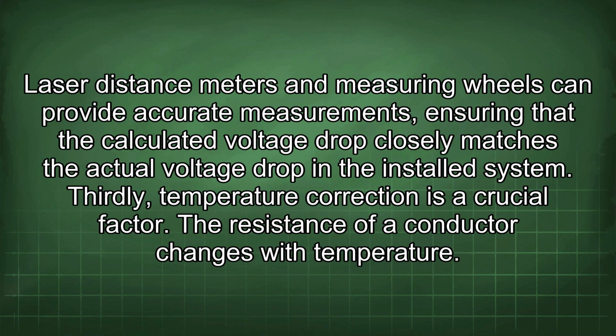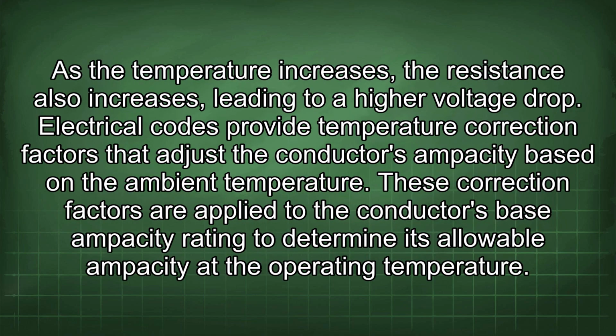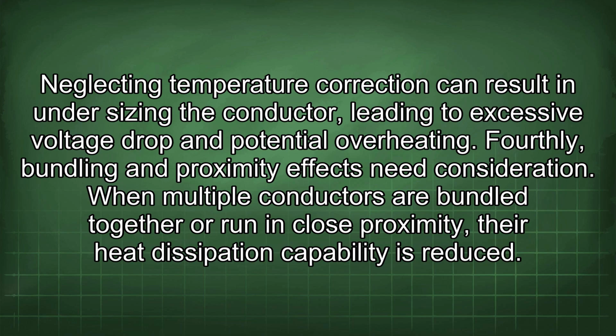Thirdly, temperature correction is a crucial factor. The resistance of a conductor changes with temperature. As the temperature increases, the resistance also increases, leading to a higher voltage drop. Electrical codes provide temperature correction factors that adjust the conductor's ampacity based on the ambient temperature. These correction factors are applied to the conductor's base ampacity rating to determine its allowable ampacity at the operating temperature. Neglecting temperature correction can result in undersizing the conductor, leading to excessive voltage drop and potential overheating.